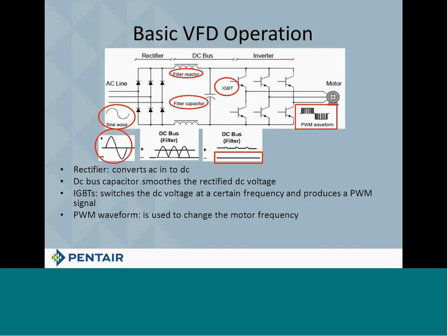You'll notice if you look way back over on the left-hand side, there's your AC sine wave. And your AC sine wave is a nice smooth up and down and back up and down again, okay? When you look at pulse width modulation, it's choppy. What it's doing is we're turning on and then off, and then on and then off, and we're changing that DC voltage to go up. We're turning it on, then off, and we're getting a spike that goes up and down, okay? So you've got to make sure that you get that sine wave to look proper.